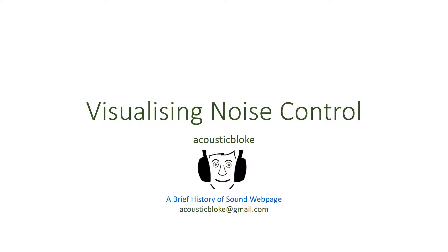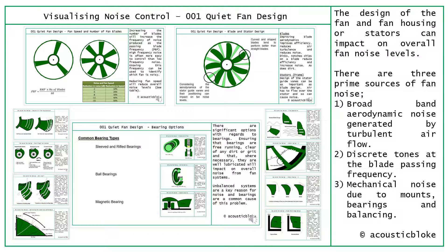Hello and welcome to Visualising Noise Control. Today we're going to be looking at noise from fans — this is the first in the series — covering the design of fans and fan housings or stators and how that can impact on overall noise. There are three primary sources of fan noise: broadband aerodynamic noise from turbulent airflow, discrete tones at the blade passing frequency, and mechanical noise due to mounts, bearings and balances.